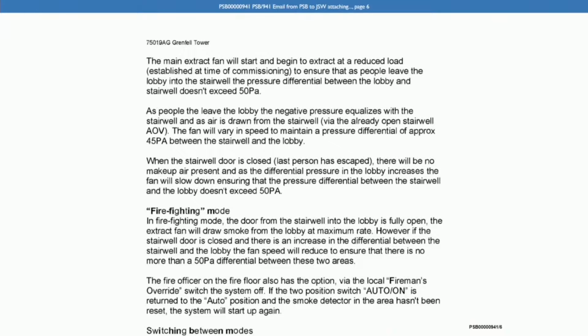Then as people leave the lobby, the negative pressure equalises within the stairwell, air is drawn from the stairwell. The fan will vary in speed to maintain a pressure differential of approximately 45 pascals between the stairwell and the lobby. When the stairwell door is closed, last person escaped, there'll be no make-up air present. And as the differential pressure in the lobby increases, the fan will slow down, ensuring that the pressure differential between the stairway and the lobby doesn't exceed 50 pascals. Now, can we agree there's a difference between this method statement and the PSB technical submission, because this method statement is specifying a bigger pressure differential than the 25 pascals in the PSB technical submission?